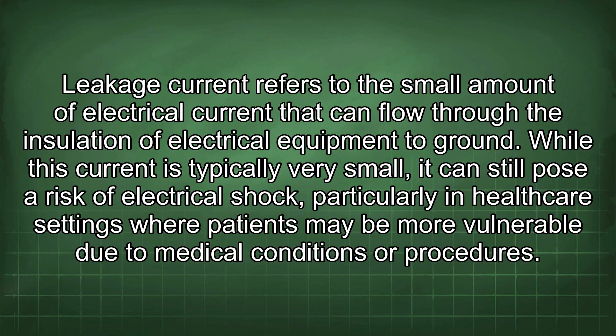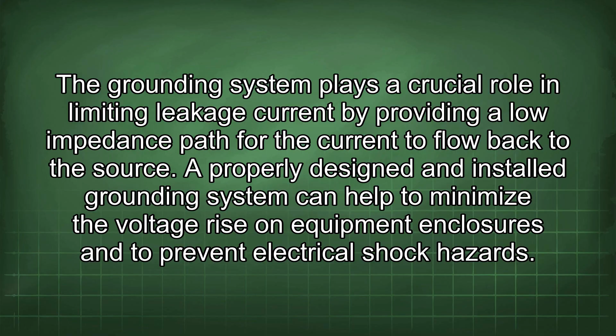The NEC sets limits on the amount of leakage current that is allowed in healthcare facilities. These limits are designed to minimize the risk of electrical shock and to ensure a safe electrical environment. The grounding system plays a crucial role in limiting leakage current by providing a low impedance path for the current to flow back to the source. A properly designed and installed grounding system can help to minimize the voltage rise on equipment enclosures and to prevent electrical shock hazards.